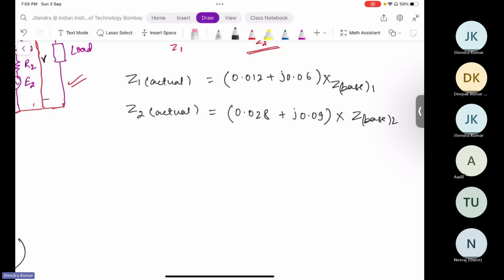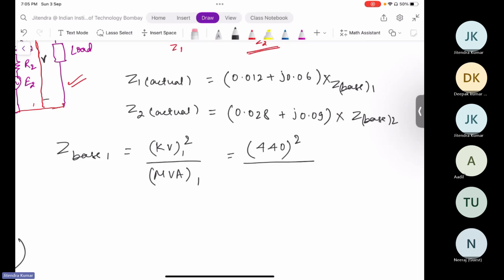Okay, so what is Z base 1? Z base 1 will be kV1 square divided by MVA1. So here we have the voltage of 440 square. We are having the 440 volt of voltage at the terminal, and kVA rating is 600 kVA. Okay, so we are calculating at the same base value.